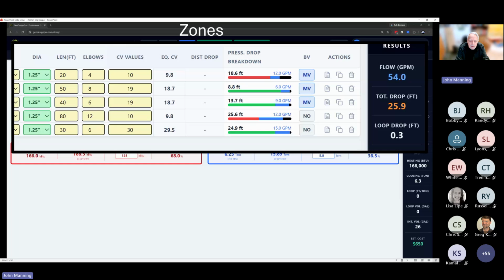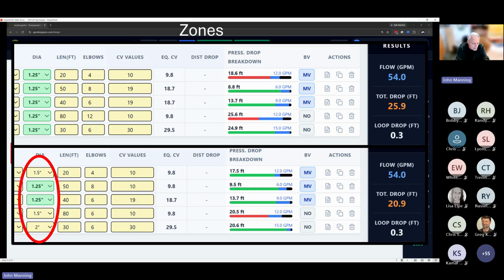And in this particular case, I'm going to take a close look at our pipe diameters. So off on the left, you'll see I've changed a couple of them, or actually 3 of them, and it changed the color coding. And the 4th one down with the red heat pump is at 20.5. Yes, I could perhaps take that pipe diameter up to 2 inch, but because it's so close in pressure drop to the number 5 heat pump, I kept it at 1.5 inches because they're closely balanced. The program will also indicate if you need a balance valve. The MV indicates a motorized valve that for variable speed heat pumps pretty much acts as a balance valve because the heat pump will control it directly. And you can dial that into min and max flow rate on your system.